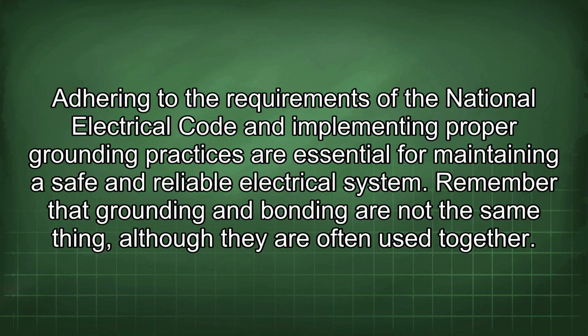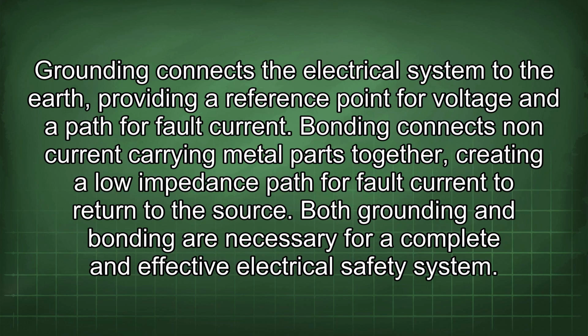and reliable electrical system. Remember that grounding and bonding are not the same thing, although they are often used together. Grounding connects the electrical system to the earth, providing a reference point for voltage and a path for fault current. Bonding connects non-current carrying metal parts together, creating a low impedance path for fault current to return to the source. Both grounding and bonding are necessary for a complete and effective electrical safety system.